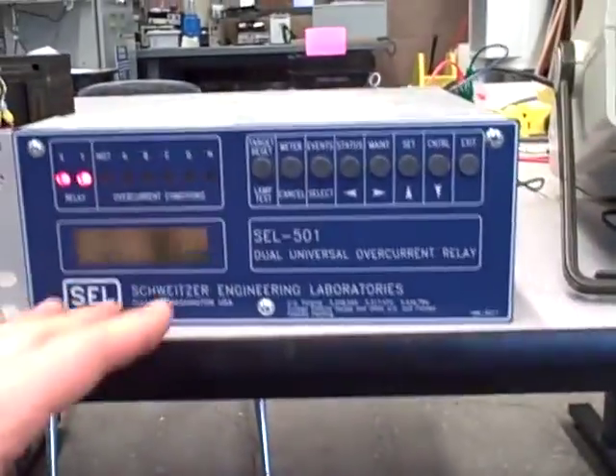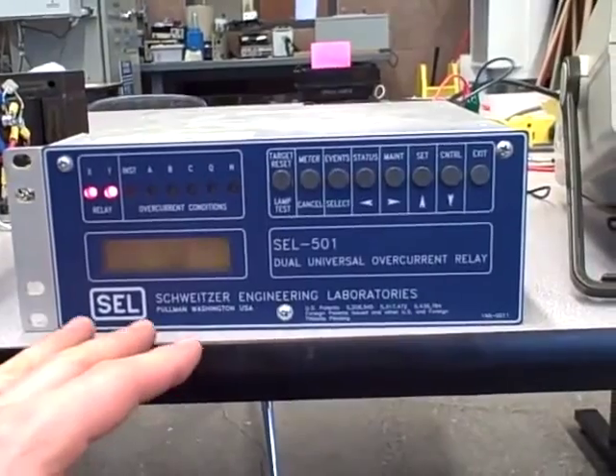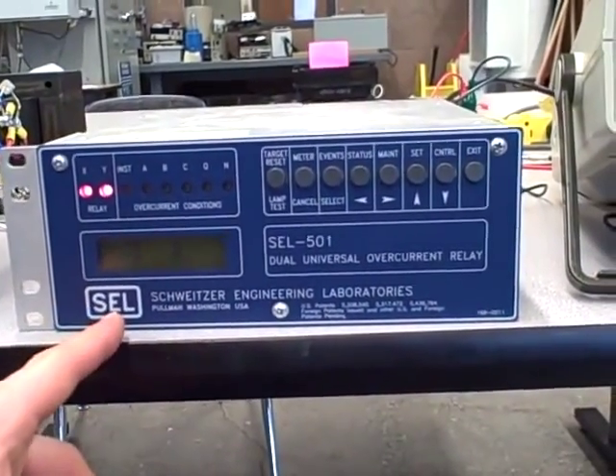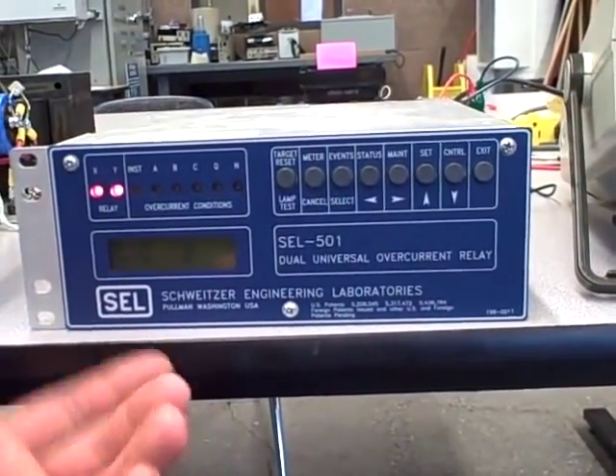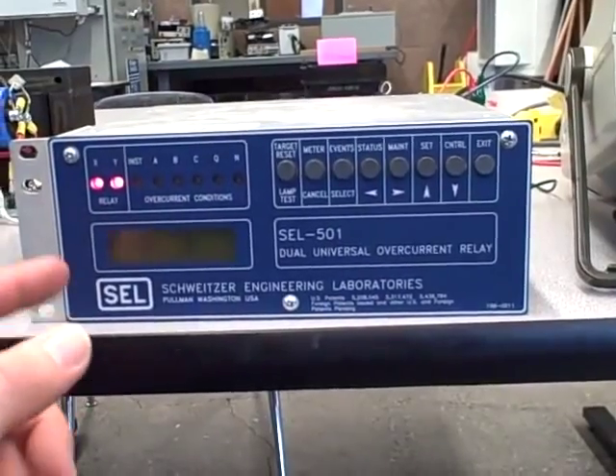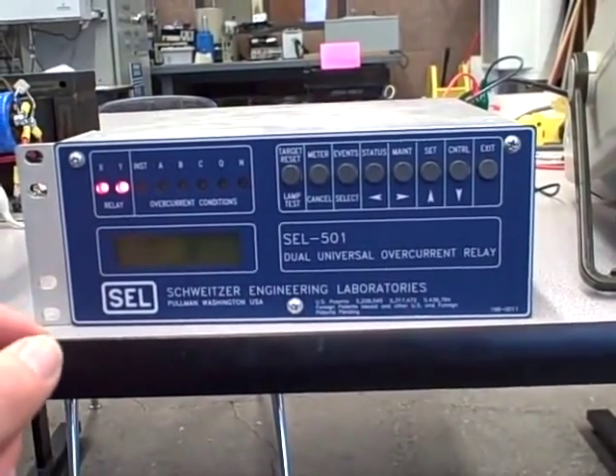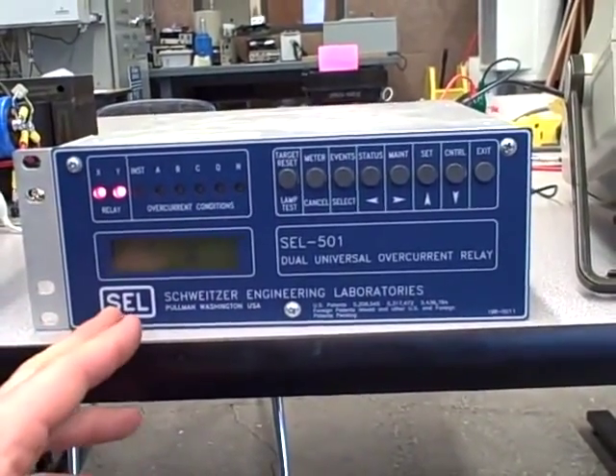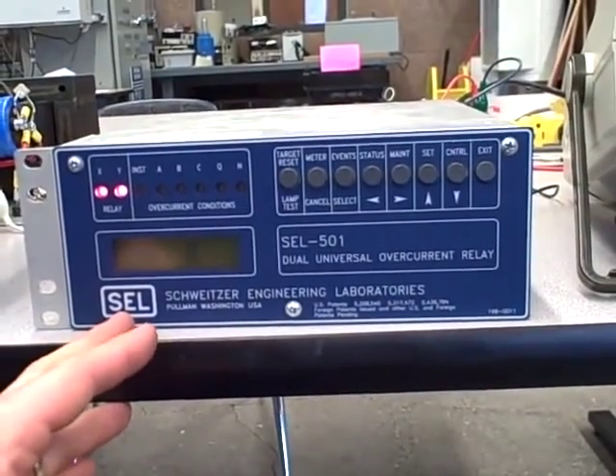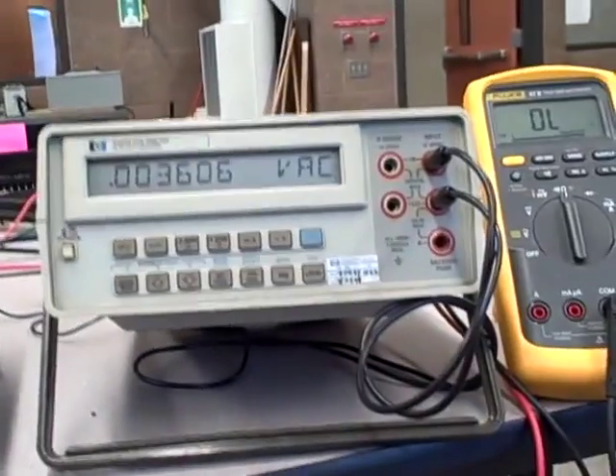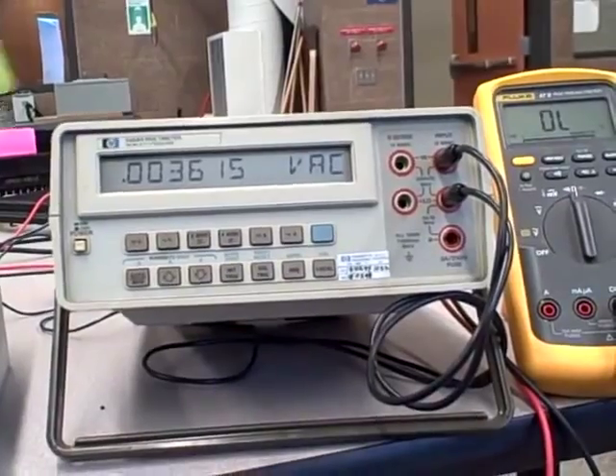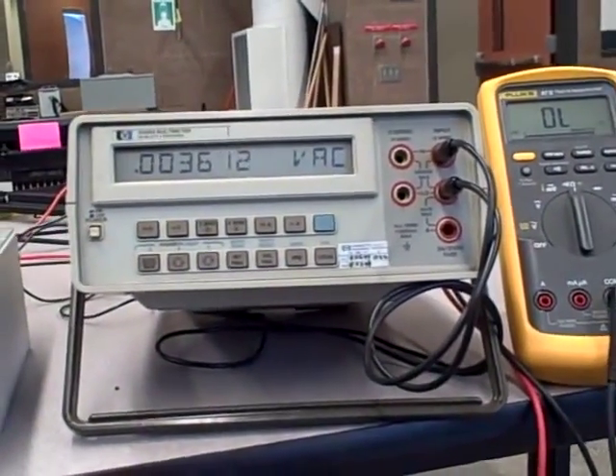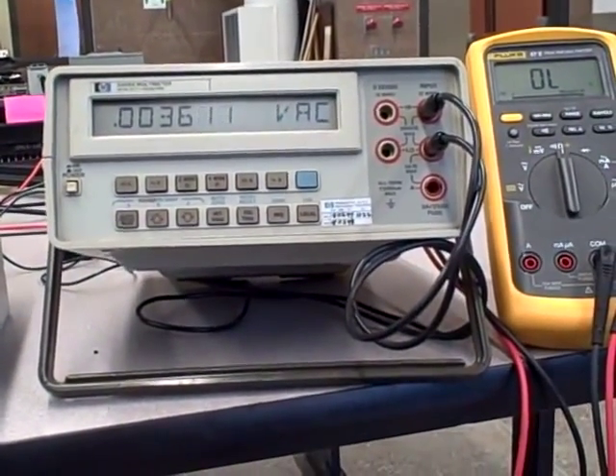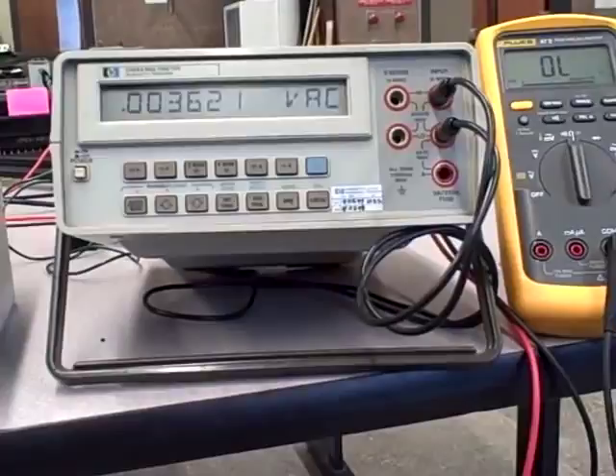But remember, this knows it's connected to a current transformer, a CT. And so into this relay, we have programmed that CT's ratio. I told this relay it's expecting a 1,000 to 5 CT ratio. So 5 amps coming into this will be interpreted as 1,000 amps line current. 3.6 amps coming in then gets interpreted as about 720 amps of line current. I have a little bit of an error on this meter, so if you run the calculations on your own, it'll be slightly off, but that's okay. I need a better quality meter here.